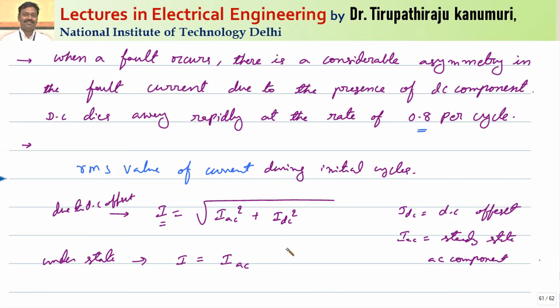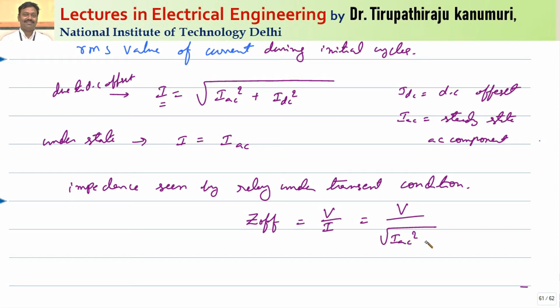So let us take the impedance seen by the relay under these transient conditions, and represent it as Z offset, the offset impedance. This will be equal to V divided by I, so this becomes V divided by square root of I_AC square plus I_DC square. We know that I_AC square plus I_DC square will be more than the normal value of current. So automatically Z under offset will be less than Z under steady state, or the Z without offset. Getting this one? So how much extra error is coming because of offset is represented by the percentage transient overreach.